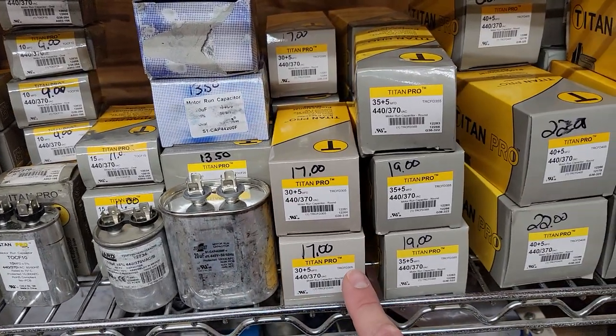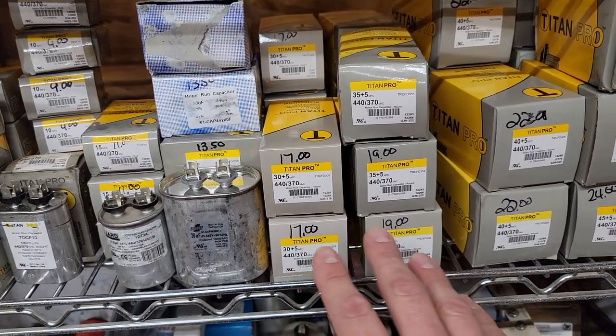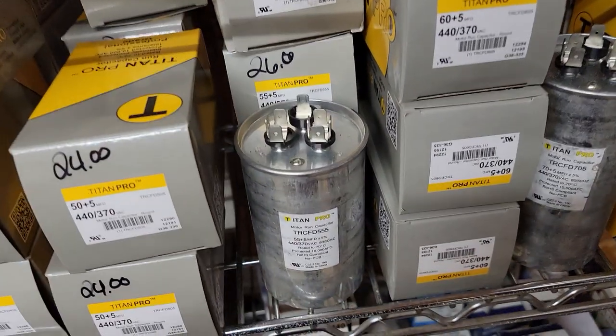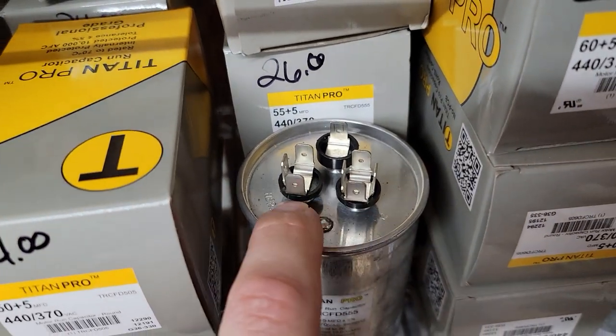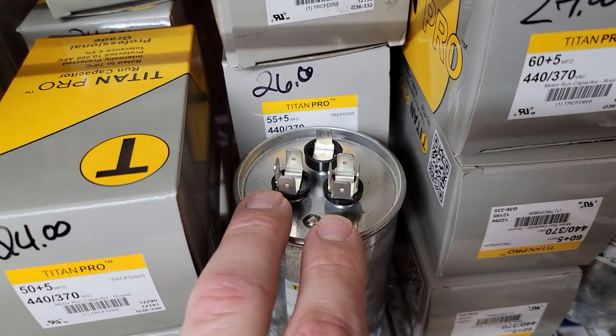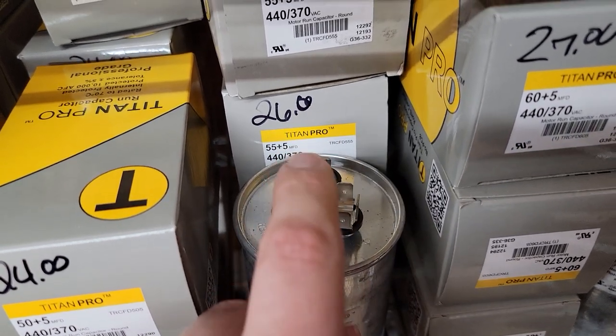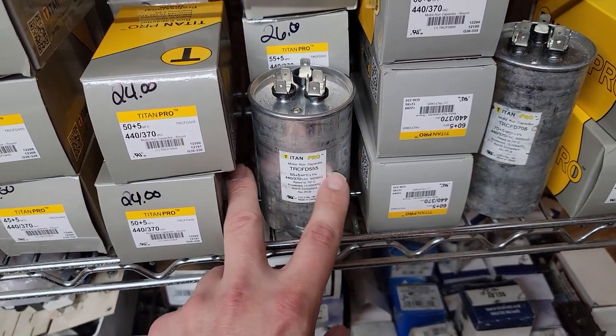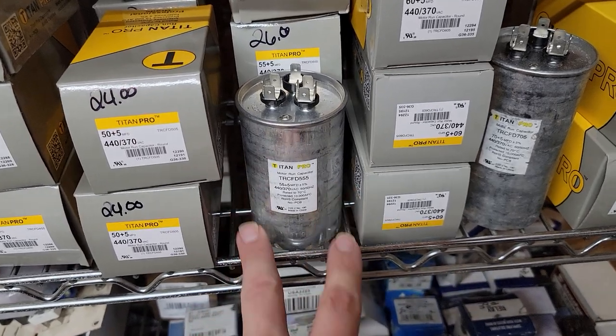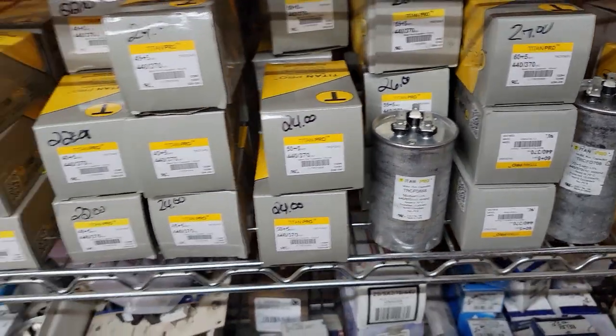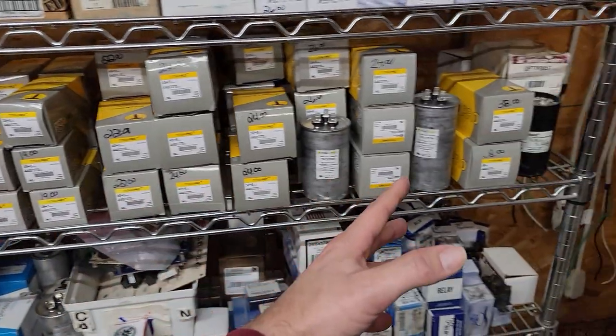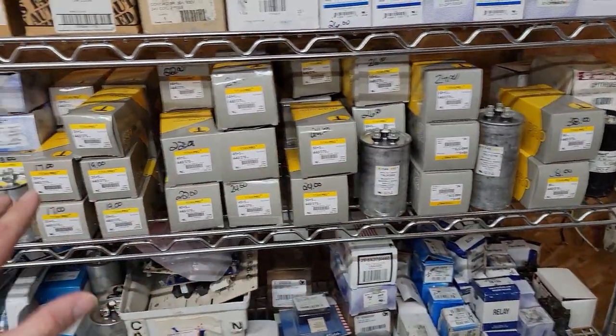5, 7.5, 10, 15, 20. This is 30 plus 5. We get into the dual capacitor. Dual capacitor means not only do you have a place for your common HERM, your compressor hookup, but also your common and your fan. So this is your fan's capacitor and your compressor in one. That's a dual capacitor. So capacitors is one of the number one most common parts that is going to have to be replaced. And it's during the summer.